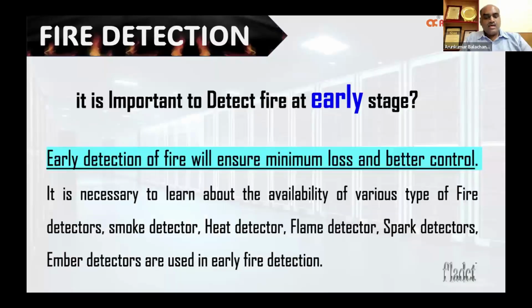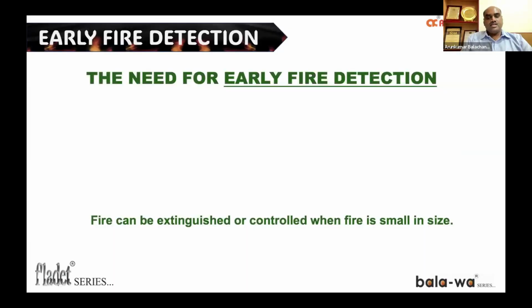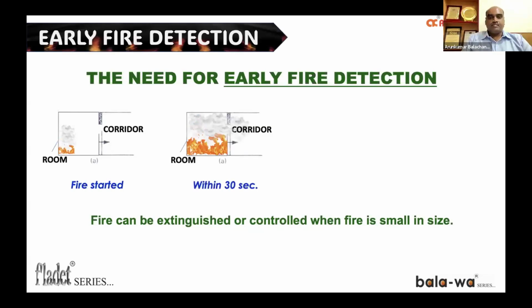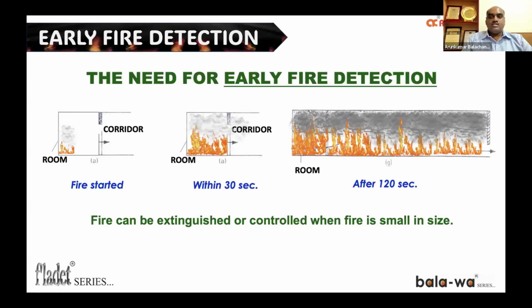When I say early fire detection, it means that we need to identify and detect the fire at the earliest possible stage. That means we are identifying the fire at the smallest stage itself. This small animation will show the spread of fire and the necessity of early fire detection. This is based on research from one of the prestigious institutes. We have a room and a corridor, and when a fire starts in one corner of the room, within 30 seconds, the entire room is engulfed in flame. And within 2 minutes, that is 120 seconds, the fire spreads to the entire corridor. In short, fire, when small in size, can be easily controlled and extinguished, which is going to be the principle for today's session.